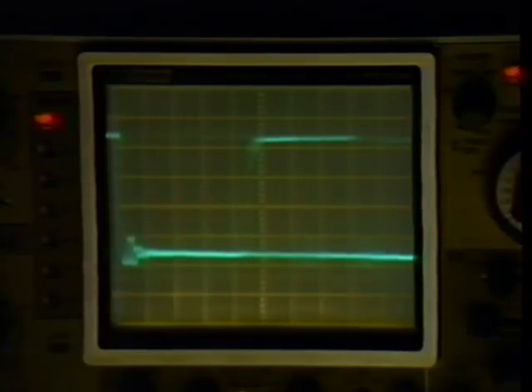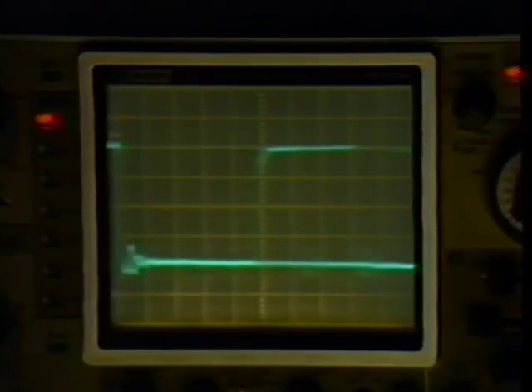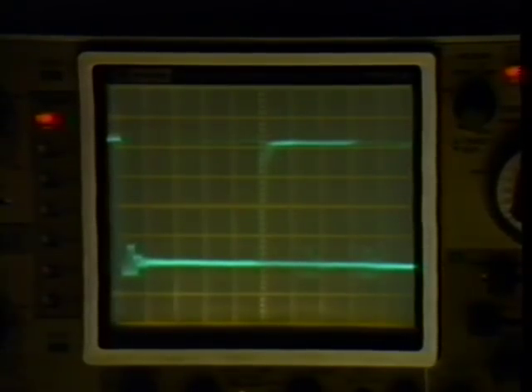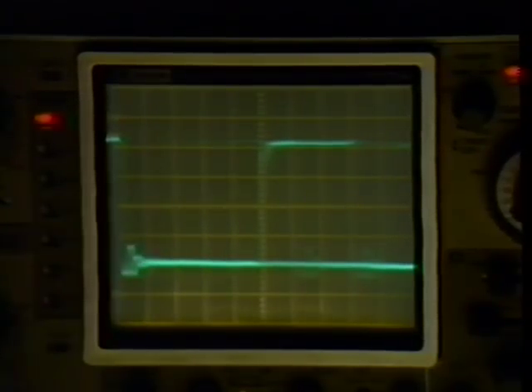Adjust the potentiometer so that the pulse is solidly low for the time specified by the diagnostics. In this case, the pulse should be 250 nanoseconds long. Always measure from the halfway point on each edge of the waveform. Keep in mind that you are adjusting for pulse width, not stability. A stable, repetitive D-Run pulse indicates incorrect alignment.